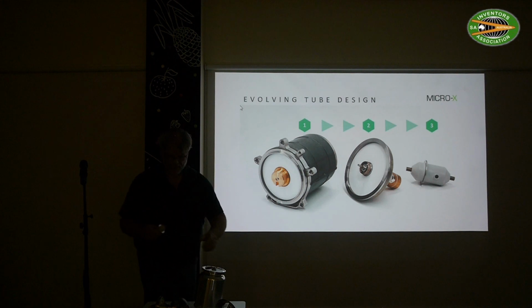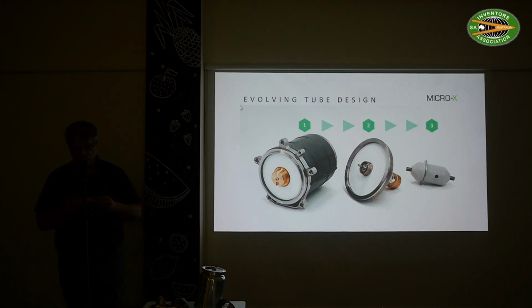And the final one we're currently working on - this is only a 3D printed model - is roughly equivalent to the X-ray tube we're developing for the CT scanner for ambulances. The idea is to have 31 of these in a row, right next to each other, with no moving parts - we just electronically switch them on and off one after the other, which lets us get a CT image as a 3D image from a person's head.